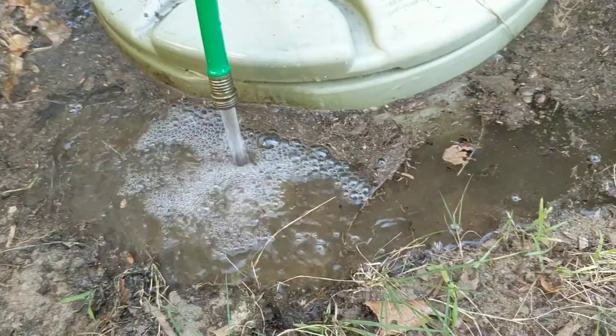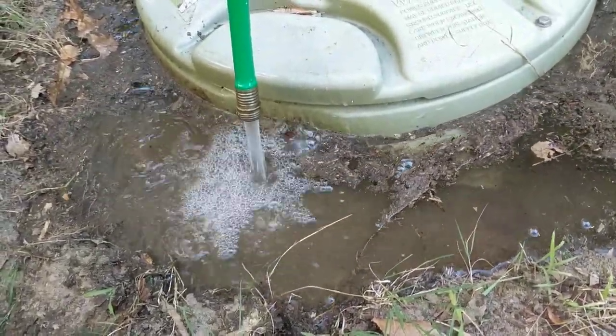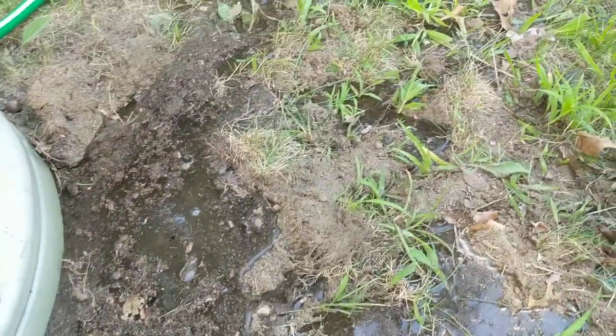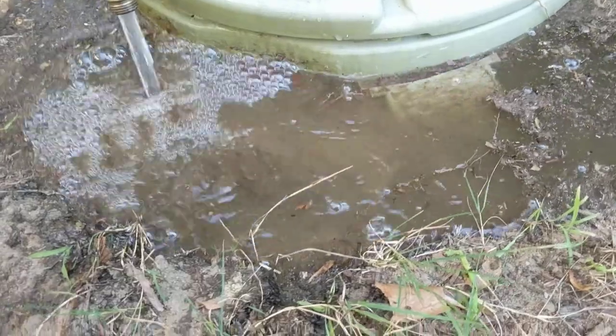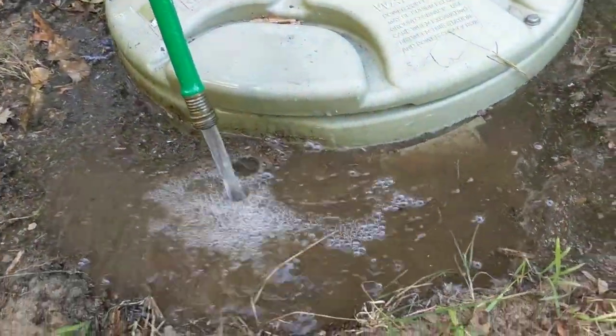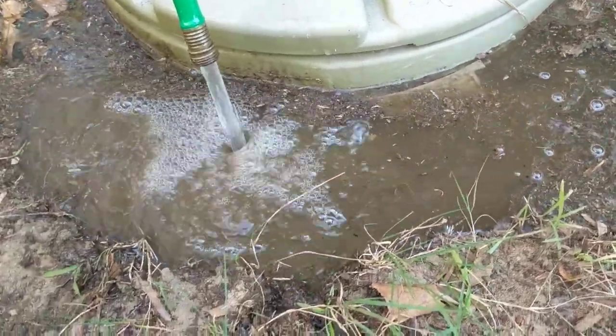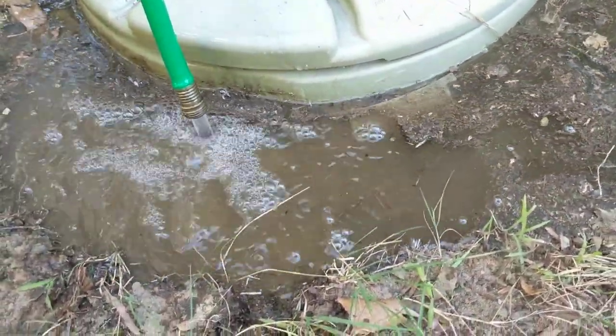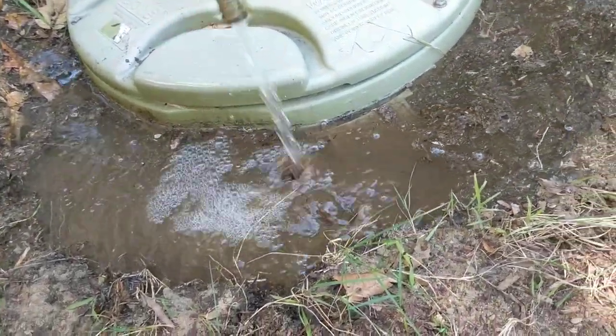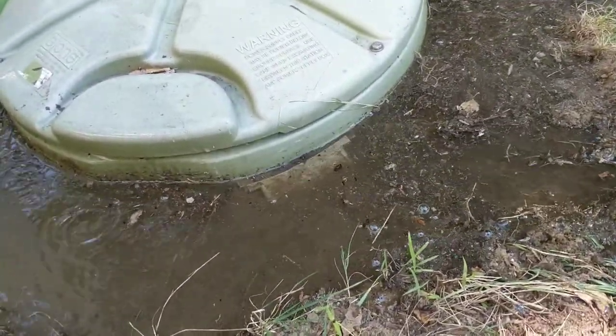Now, if Marlene came out one day and took a look at her pump and it looked like this, she would know that she had a failure and that it's been overflowing, okay? Right. And this can happen. Sometimes it fails without the alarm going off and you don't know that it failed until you smell it. Or if the pump is really close to your house like this one, you'd actually see it. Okay, so this is going to be a pass, okay? Yay! You can go turn off your hose now, or you can throw it aside if you have no concern about it.